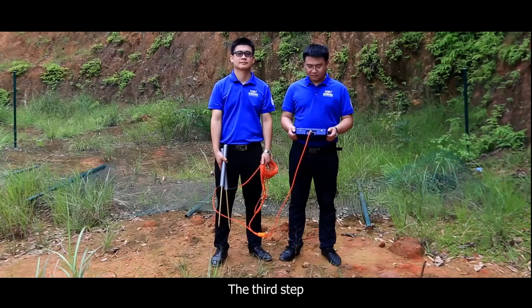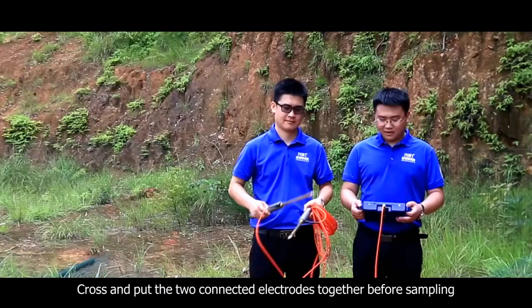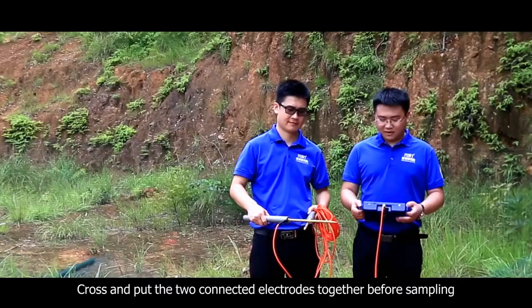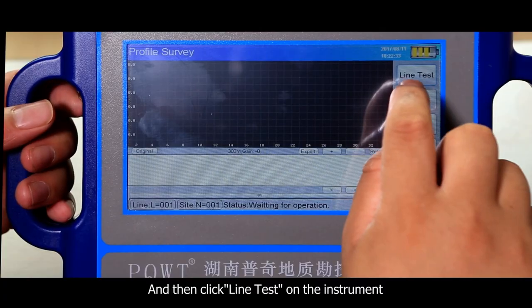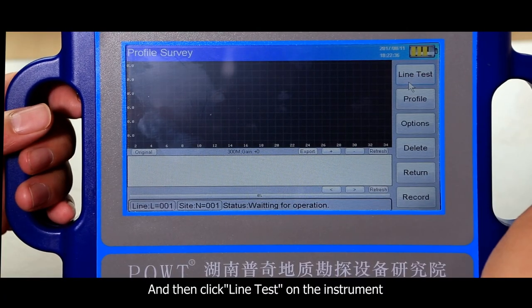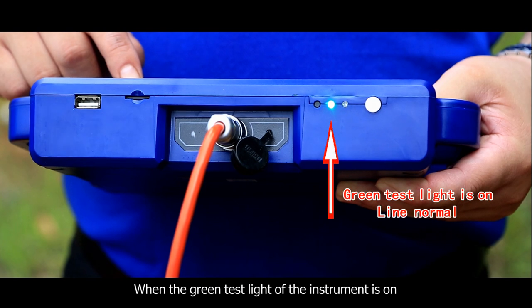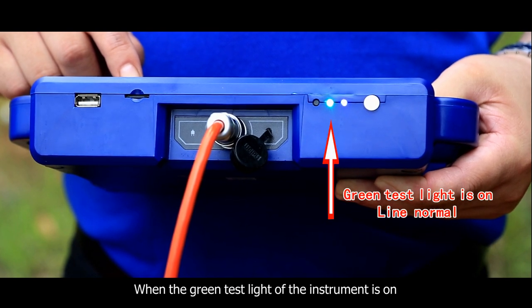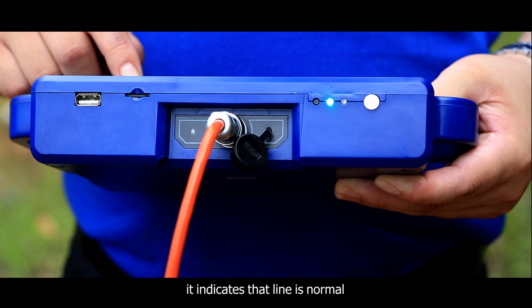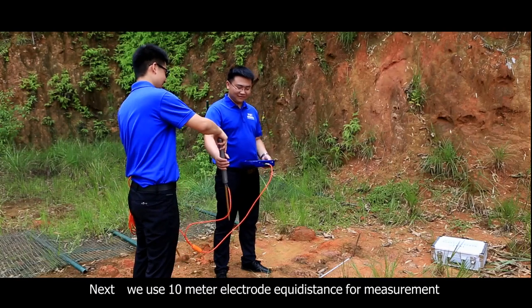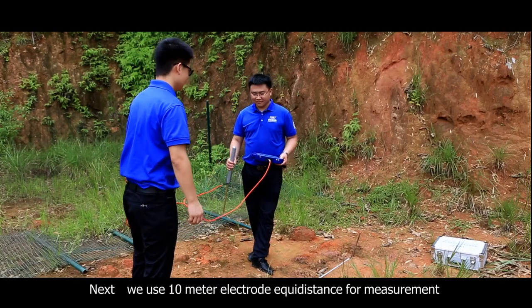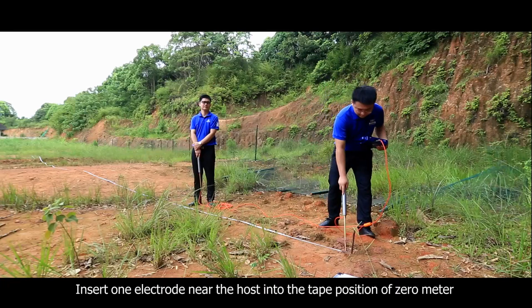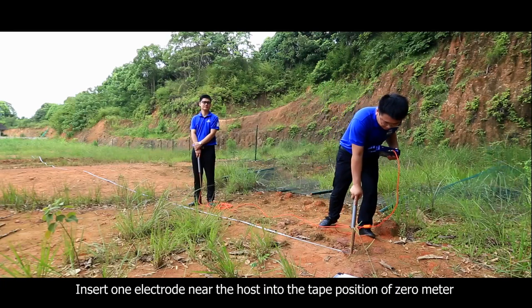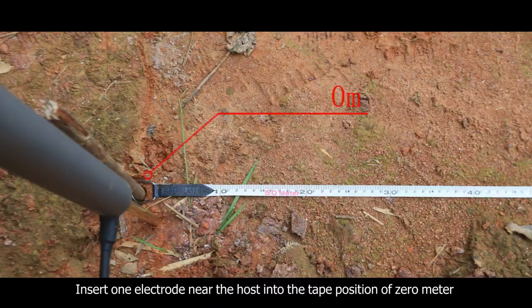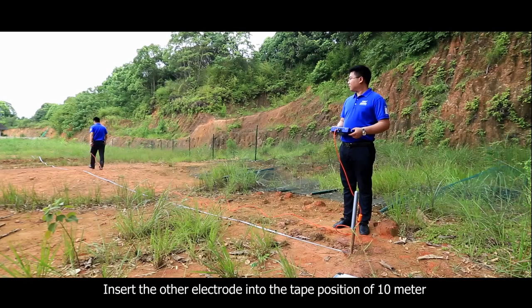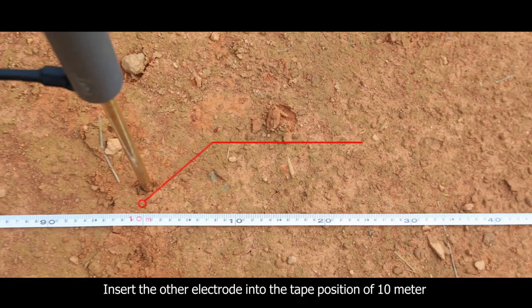The third step, cross and put the two connected electrodes together before sampling. And then click line test on the instrument. When the green test light of the instrument is on, it indicates that line is normal. Next, we use 10-meter electrode equidistance for measurement. Insert one electrode near the host into the tape position of 0 meter. Insert the other electrode into the tape position of 10 meter.